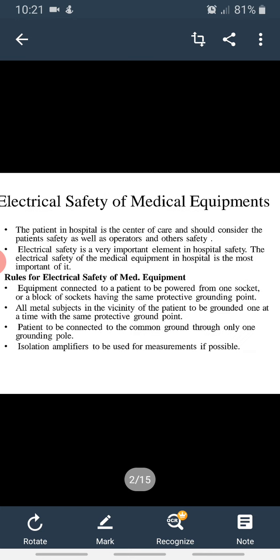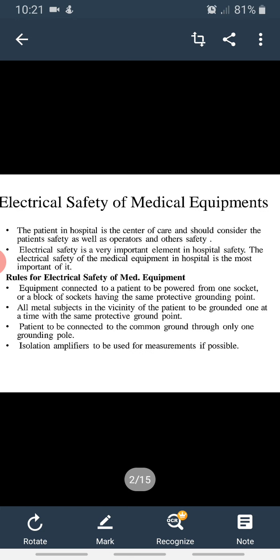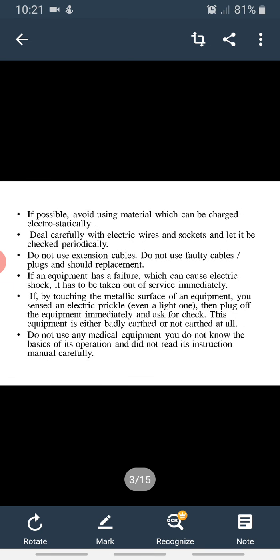The equipments connected to a patient are to be powered from one socket or a block of sockets having the same protective grounding points. All the metal subjects in the vicinity of the patient are to be grounded one at a time with the same protective ground point, and the patient is to be connected to a common ground through only one grounding pole. Isolation amplifier is to be used for the measurement if possible, avoid using materials which can be charged electrostatically, and deal carefully with electric wires and sockets and let them be checked periodically.